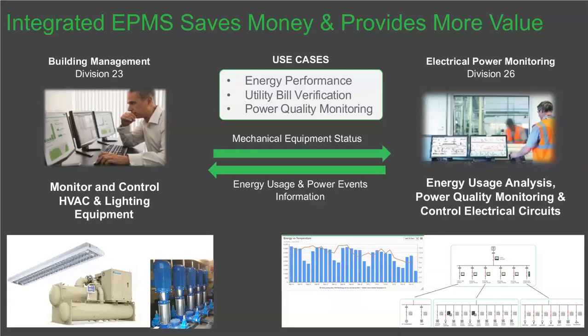When you integrate the two, there are other benefits beyond just KW and KWH. You can look at energy performance, utility bill verification, and even power quality. There's a lot more information in the meter than just a Modbus register, available if you have the right software tools to extract it. So why not connect into that extra level to get the extra information that was already available at the meter level.